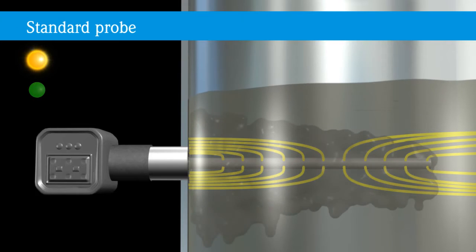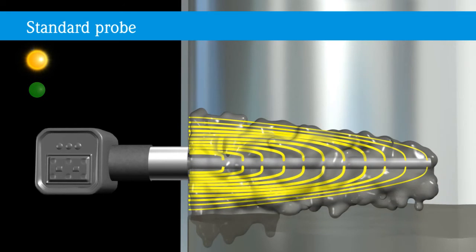If conductive build-up sticks to the probe, this is recognized as a change in capacity in relation to air, comparable to a product. In this case, the lines of flux run directly through the build-up to the tank wall. Even if the product does not cover the probe, it reports covering erroneously.